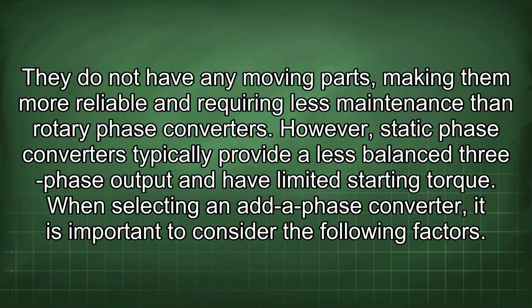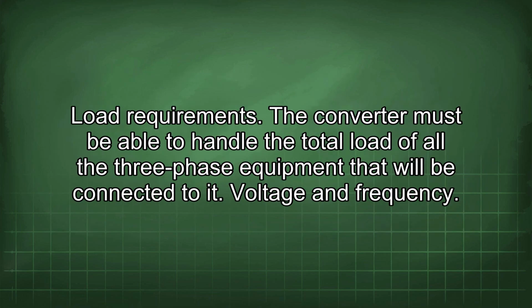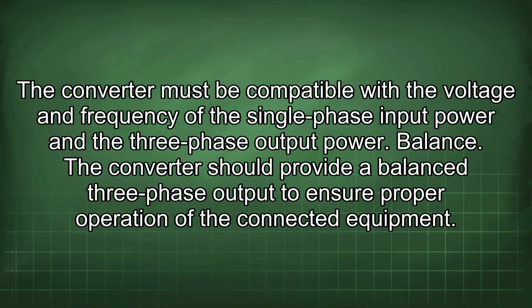When selecting an add-a-phase converter, it is important to consider the following factors. Load requirements. The converter must be able to handle the total load of all the three-phase equipment that will be connected to it. Voltage and frequency. The converter must be compatible with the voltage and frequency of the single-phase input power and the three-phase output power.